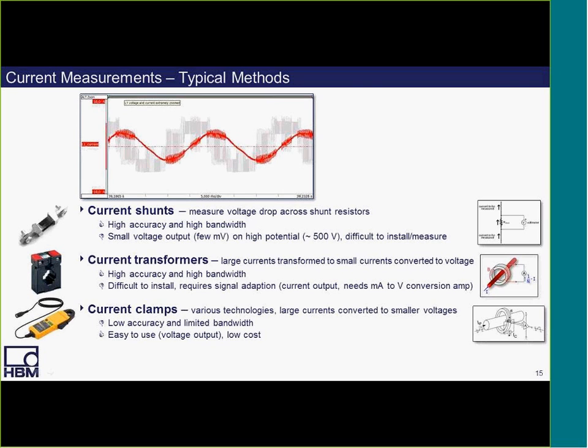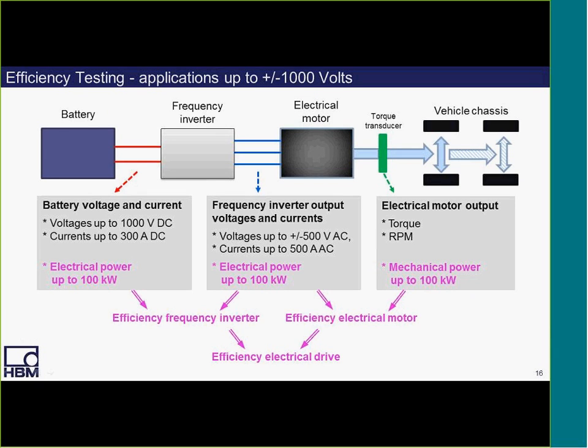Well, now that we've covered some of the more important high-voltage terminology, what we're going to do is apply what we've covered to each of the more common high-power measurement applications we've mentioned earlier, including efficiency testing, switchgear testing, high-voltage impulse testing, and lightning monitoring. So here, we'll start with efficiency testing. This could be either a vehicle's electric drivetrain or the drivetrain of an aircraft's auxiliary power unit. Regardless, this can be any power application that requires the measurement up to plus minus 1,000 volts.